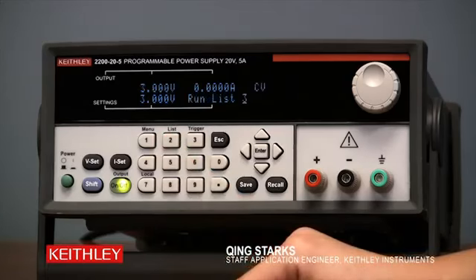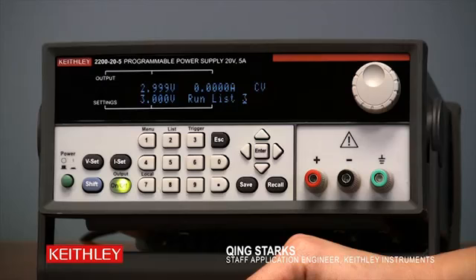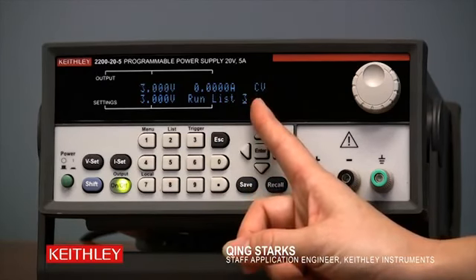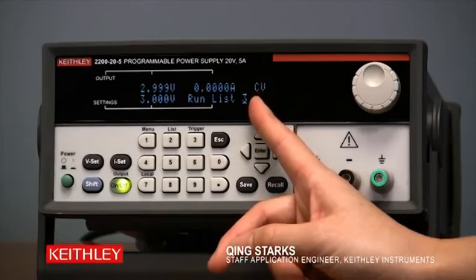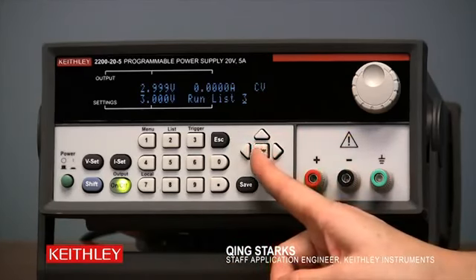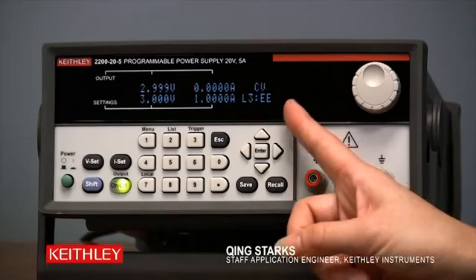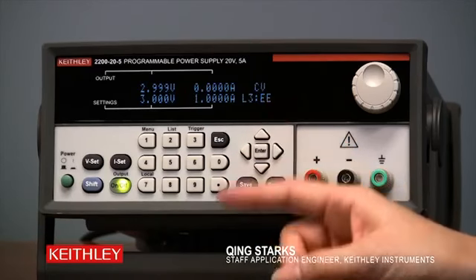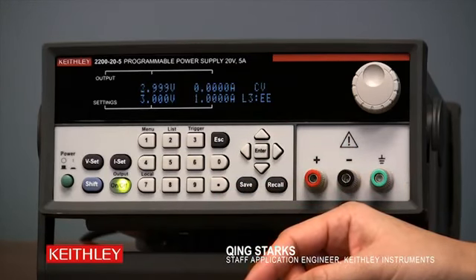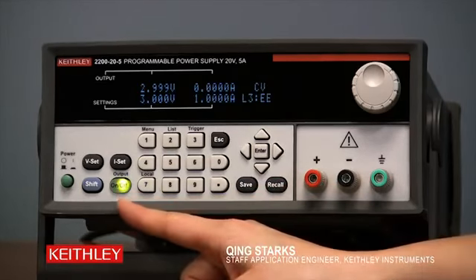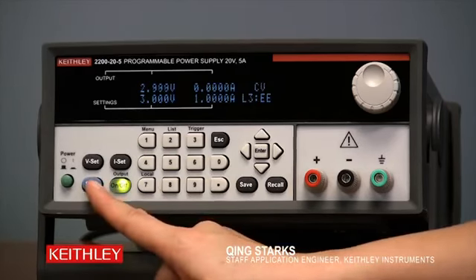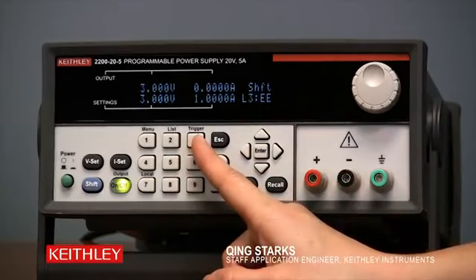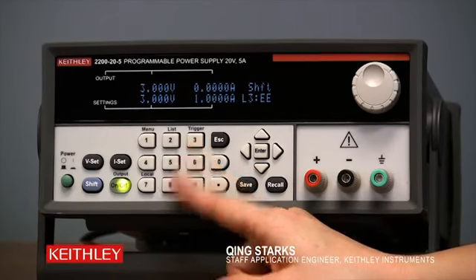Press 2. The display will prompt you to run the memory location where the list is stored. Since we stored it in memory location 3, we're happy with the 3 setting. We'll just press Enter. Now the display will show you L3:EE, which means the power supply is ready to execute lists in memory location 3. To trigger the start of the run, we'll have to press Shift Trigger. So Shift, and the display is showing shift, and Trigger, which is numeric keypad 3, press 3.